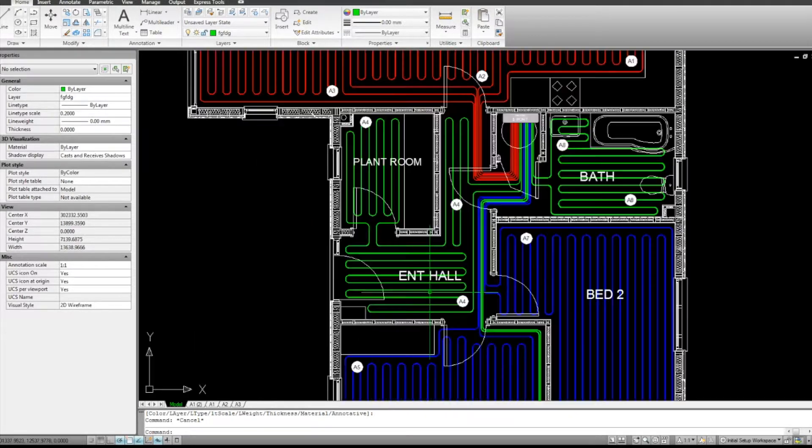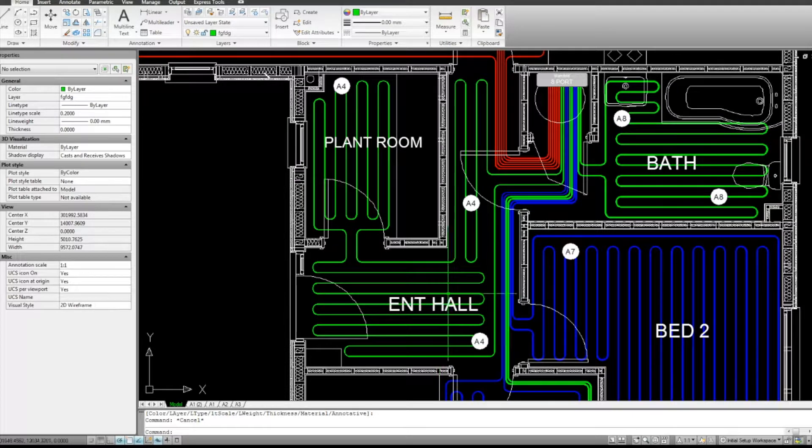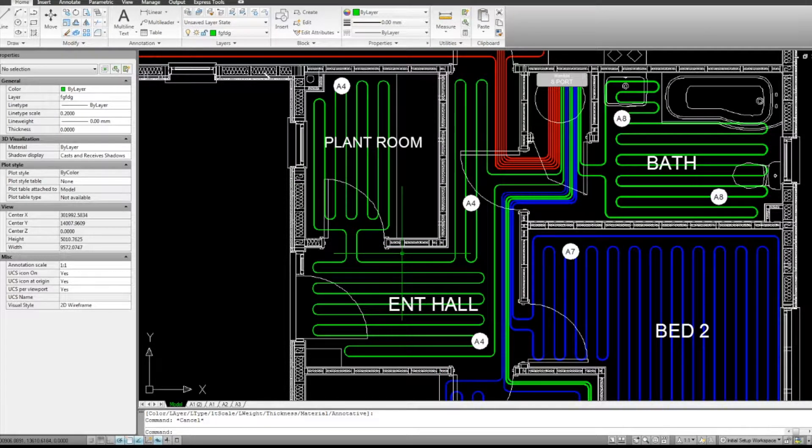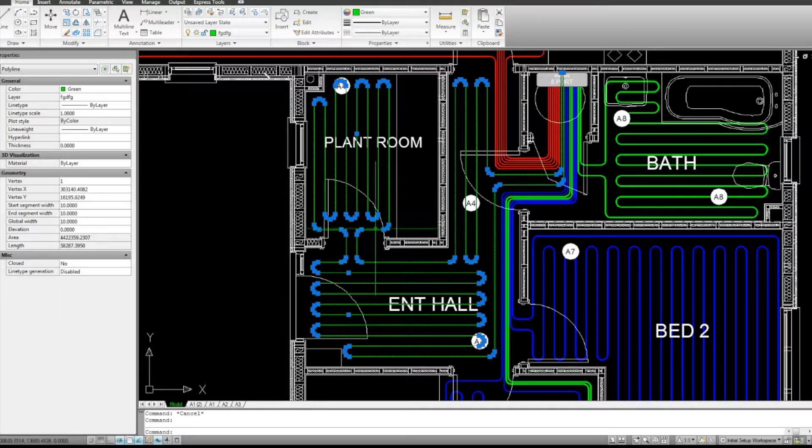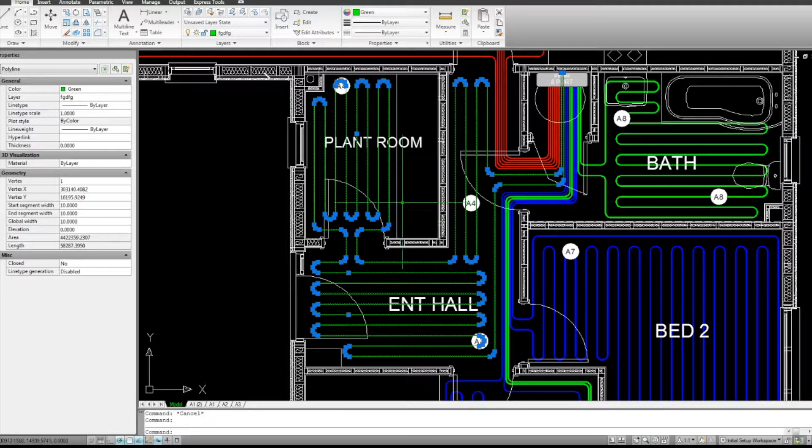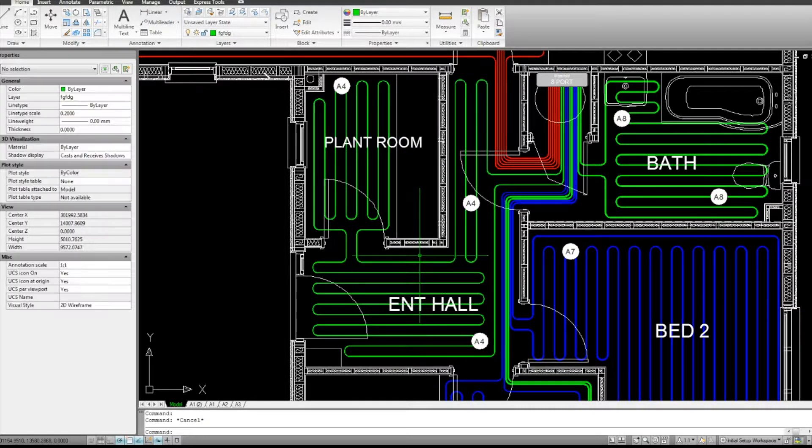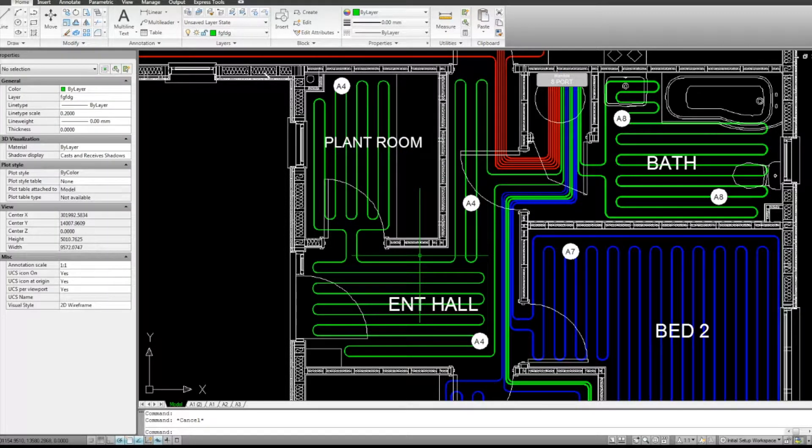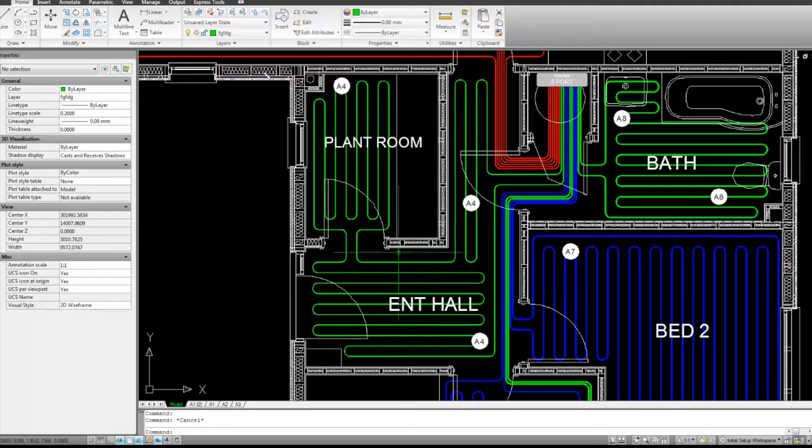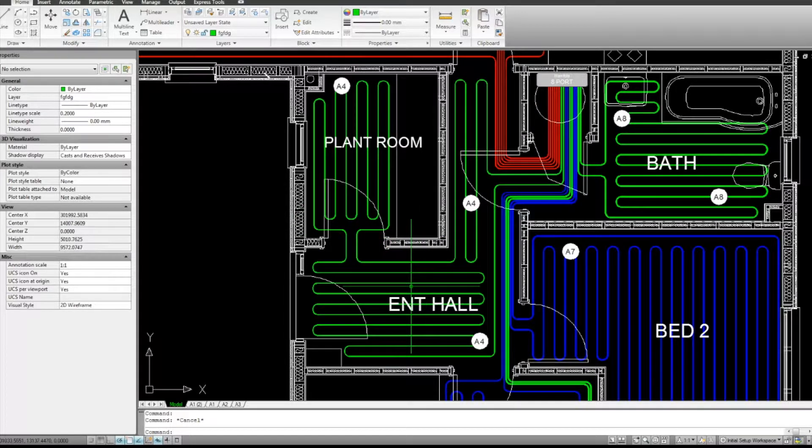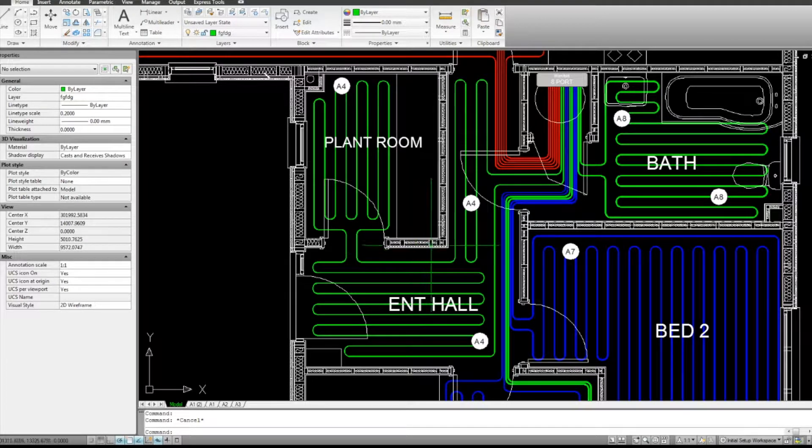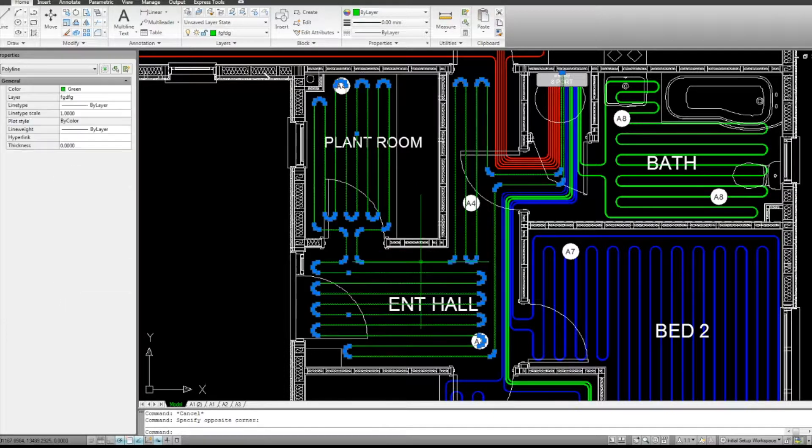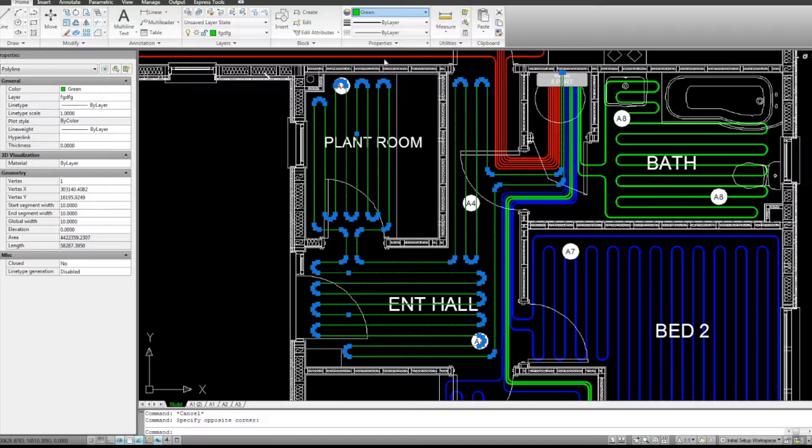So here you can see we've got an entrance hall and a plant room. They're both quite small areas. So what the designers have done here is they've actually used one circuit to control both rooms. What this means for zoning is that they can never be controlled independently. So the plant room will never be a different temperature to the entrance hall. Depending on where you locate the thermostat, that will pick up the temperature for both areas. So this would be our second zone.